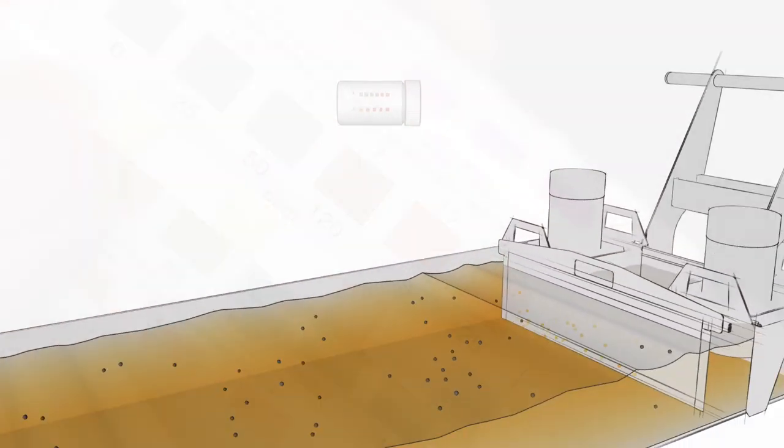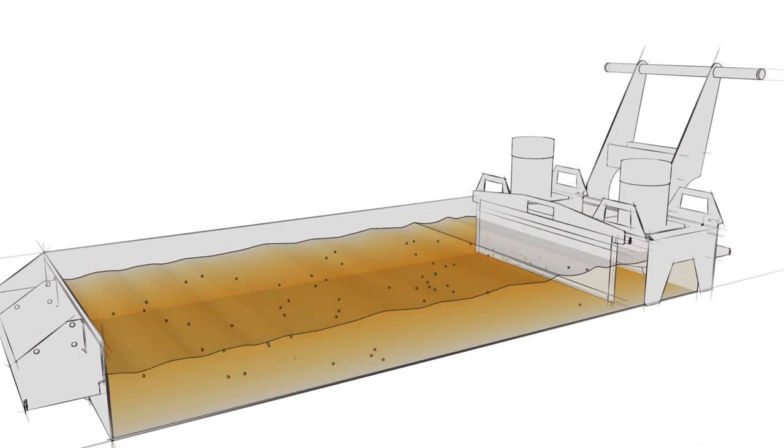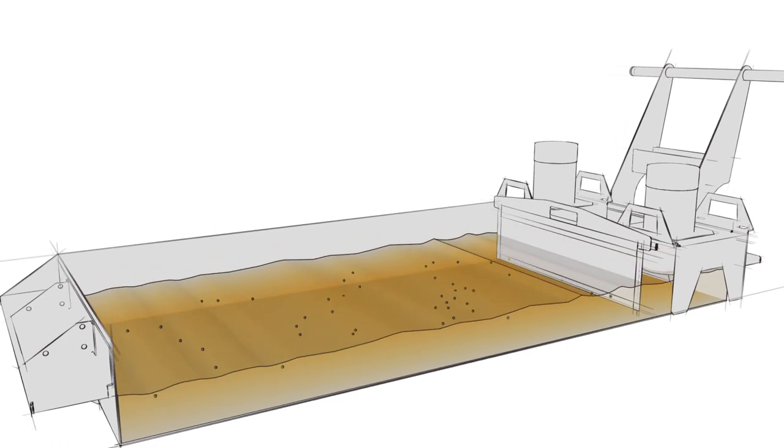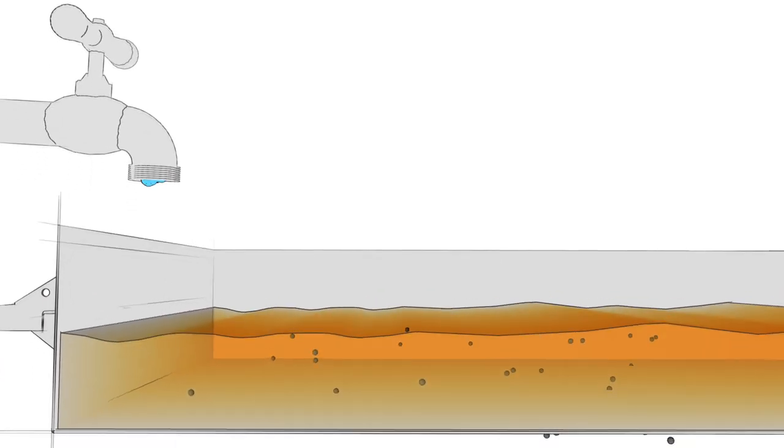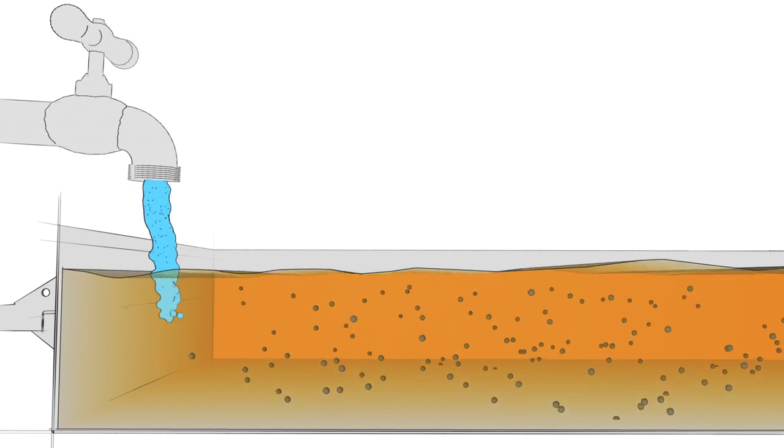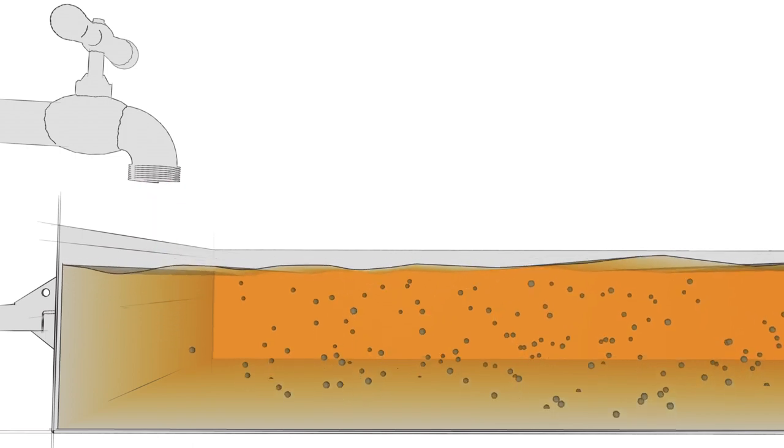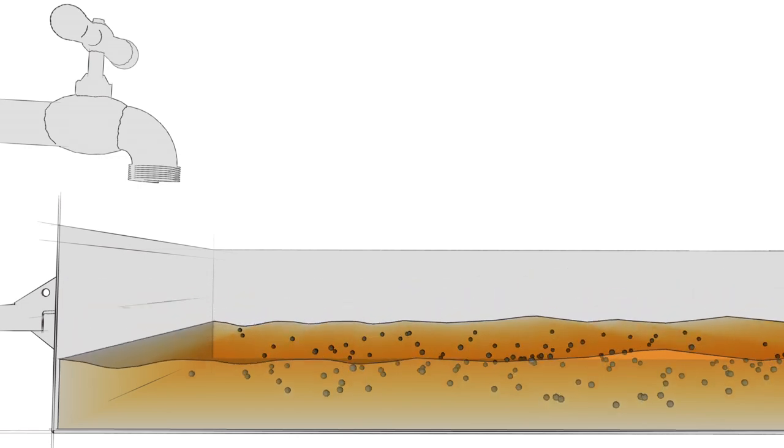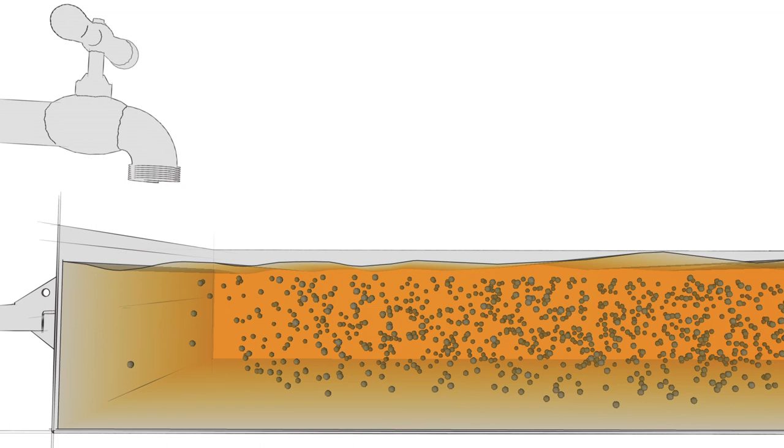So, how does the coolant get to this high hardness level? Over time, the water in the coolant evaporates away. But if tap water is used, the hard minerals in the water do not evaporate. Each time you top up the tank with tap water, a new batch of minerals is added to the mixture. After a few rounds of this evaporate and top up cycle, well, you've got a tank packed with minerals and your coolant may be ruined.